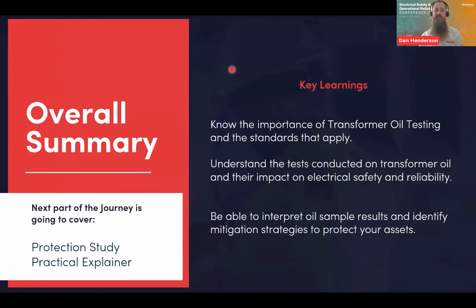Yeah, I mean, hopefully, sorry to rush through those examples. No, hopefully because of what we've covered, you can see the links between the different tests, the different output results, and then the key things we wanted you to take away was knowing the importance of the transformer oil testing and the standards that apply. Making sure you're doing them to a standard is the most important thing, especially in your geographical location, if there's any differences. But make sure they're to a standard, not just an internal one. Make sure it is to a recognized standard.